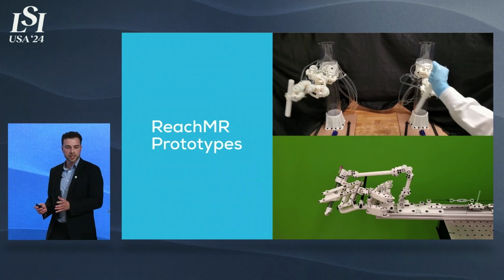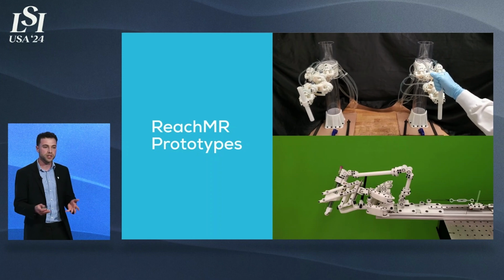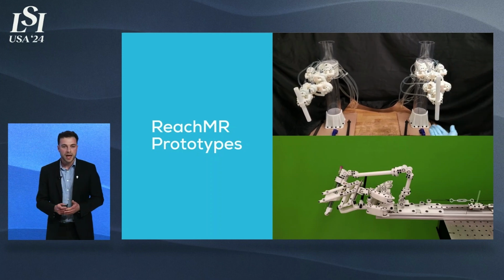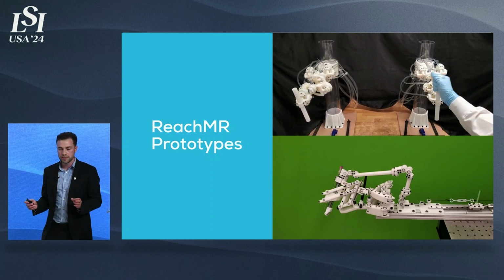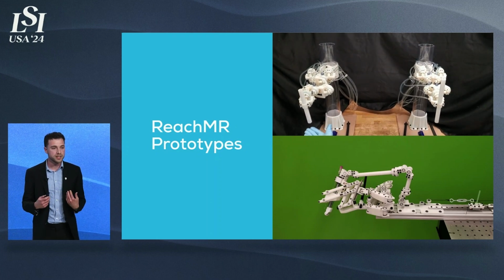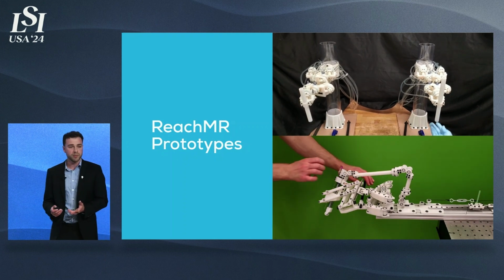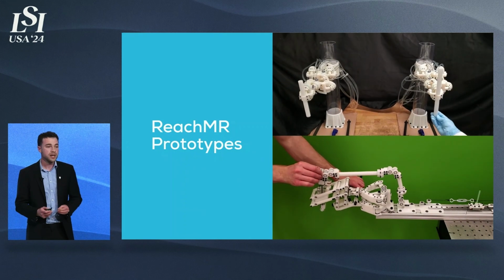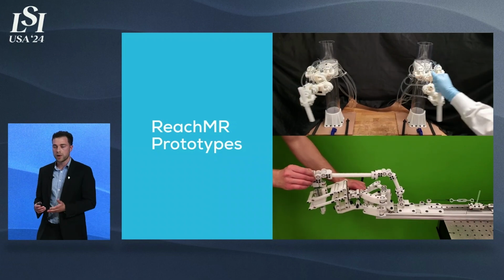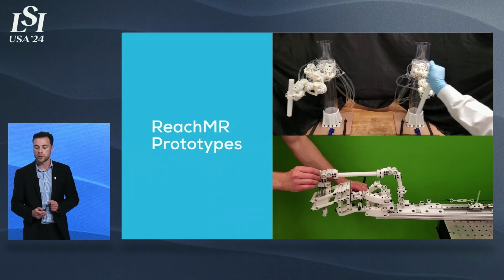This would actually be pretty tricky to do even with a traditional robotic system, but especially with something that works inside the MRI scanner. And a key point, there are no motors, no pumps. This is a fully mechanical system. Motions propagate through our custom hydraulics from the input to the output. We subsequently made a much more compact device. It's a 5-axis system, XY translation, needle advancement, and 2 angles of rotation through a remote center of motion.